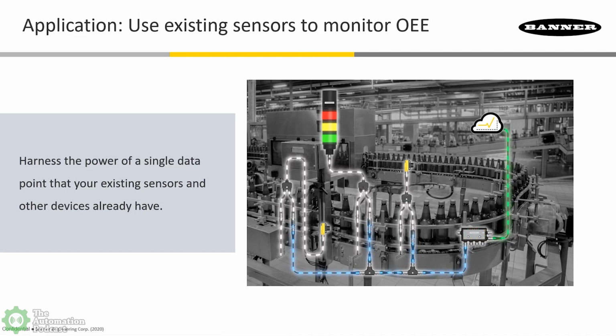By using just one of those parallel wired M12 T's, you could have multiple dozens of sensors going back on that same branch, into a single port on that controller, a single M12. So you could have discrete, analog, vibration sensors, temperature sensors, or a mixture of all of them going back on that single branch to a single port on the DXM R90. That's really powerful—being able to bring in not just one sensor signal, but multiple different sensor signals to a single port on the DXM R90.